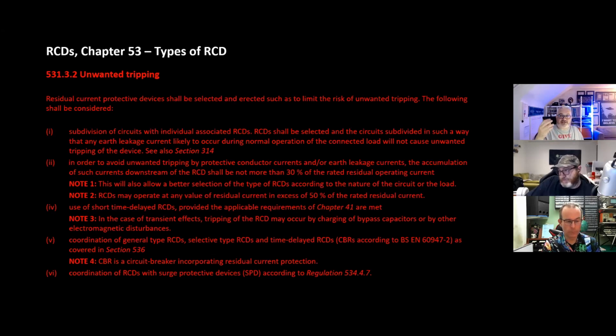RCDs should be selected and the circuit subdivided in a way that any leakage likely to occur in normal operation of the connected load will not cause unwanted tripping. So not fault current, just normal operation. In order to avoid unwanted tripping by protective conductor currents and/or earth leakage currents, the accumulation of such currents through the RCD should not be more than 30% of the rated residual operating current. So for a 30 milliamp, it was no more than 9 milliamps basically per circuit, which everyone went, where's the guidance? Where's the information? Where's the leakage information? It caused chaos and it just kept people away from going down the RCBO route.